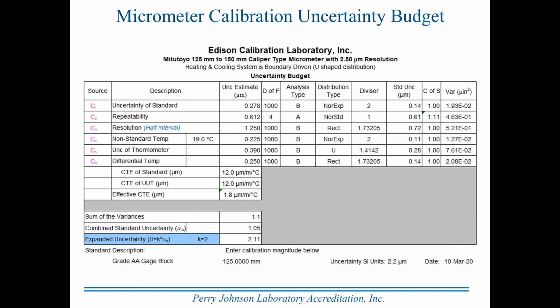But this is an example of a budget that would be totally self-contained and allow you to put in pieces of information that you can arrive at by straightforward means. You can find out what the coefficients of thermal expansion are. You can find out what the uncertainty from the calibration of the standard was and the uncertainty due to the calibration of the temperature measurement device. You can arrive at a reasonable number for differential temperature.